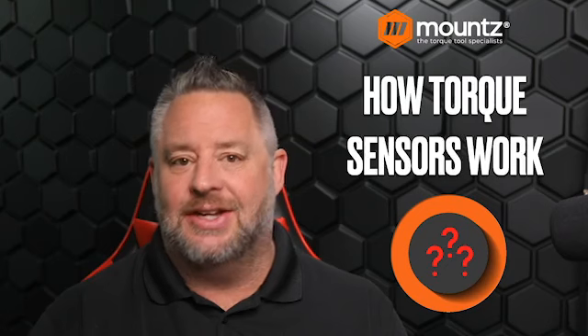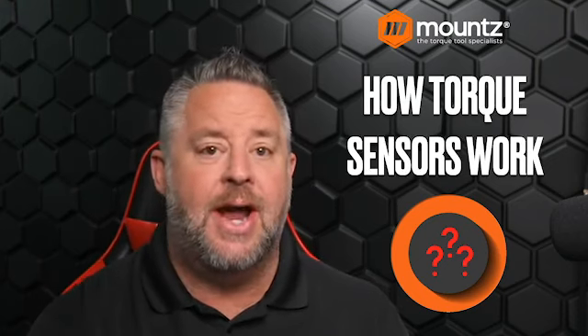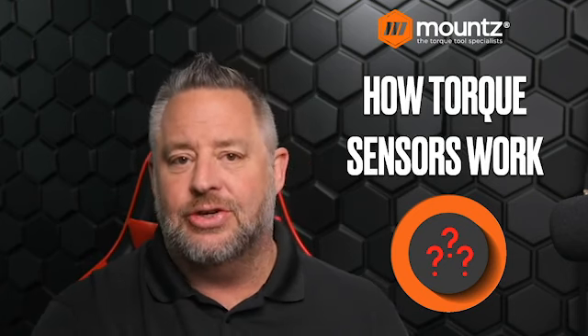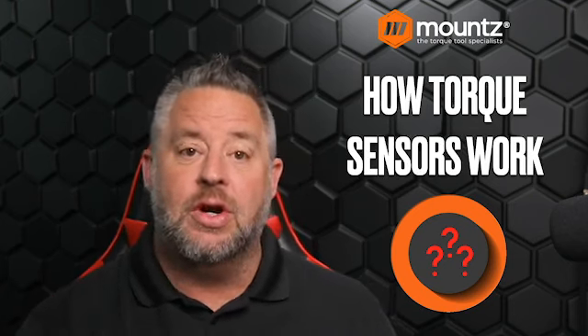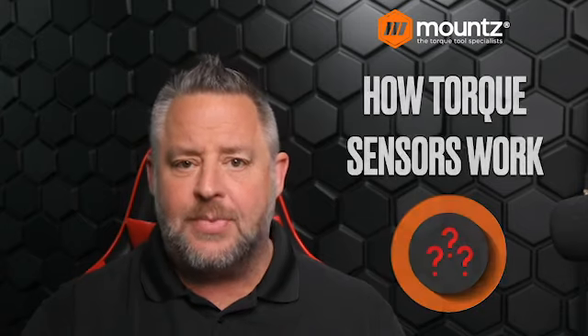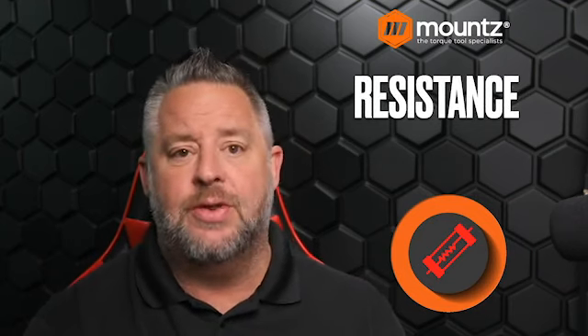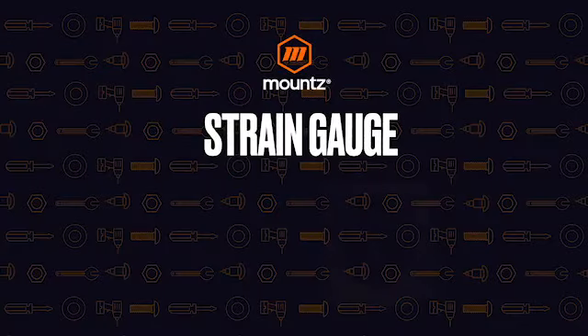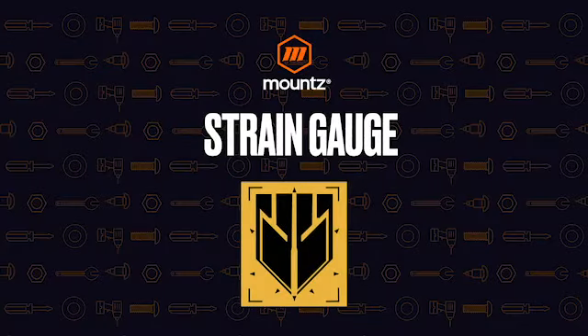Now, how does a torque sensor actually work? So we are taking an analog signal that is being generated by a tool, and then we are converting that to a digital signal that is giving us a readout of what the torque was that tool applied. And so how does this actually function? It's all done through the use of resistance measurement. So there is a device, you may be familiar with it, maybe not, but a strain gauge is an electrified circuit. It's very small, less than a postage stamp size of a circuit.